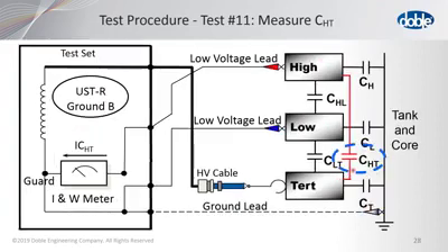Now, test number 11, we measure the interwinding insulation between the tertiary and high, and notice that we only measure that one circuit. Everything else is guarded. One thing I should note, be very careful when you move to the tertiary and you're energizing the tertiary, because it may have a much lower voltage rating than the high and the low voltage windings. If it's 4160, you do not want to put 10 kV on it. You want to put 2 kV only.